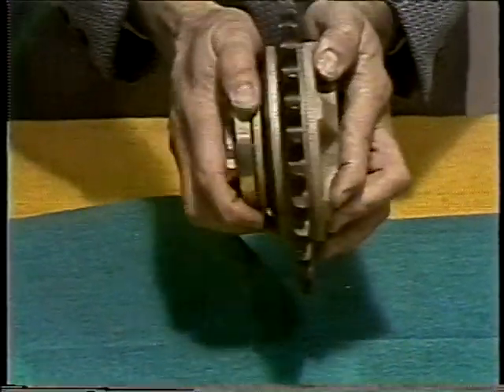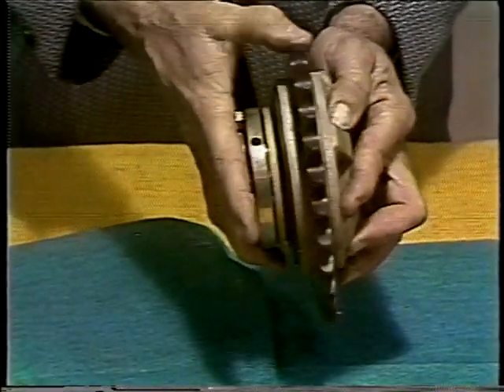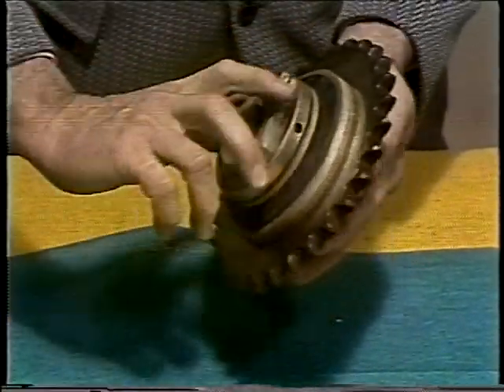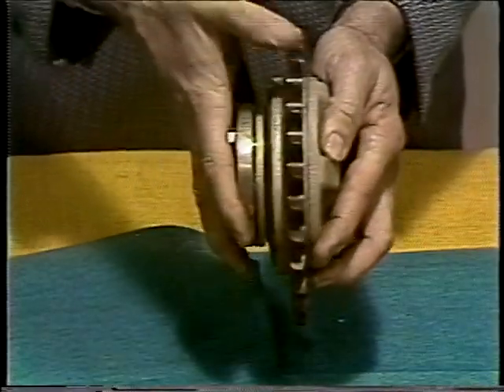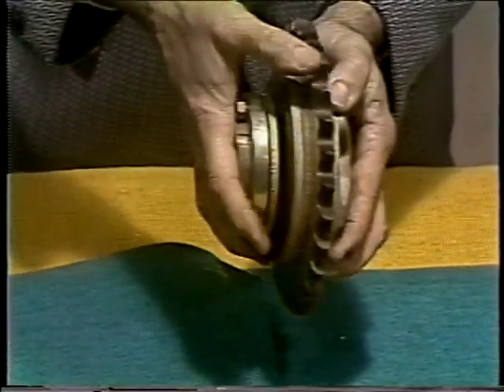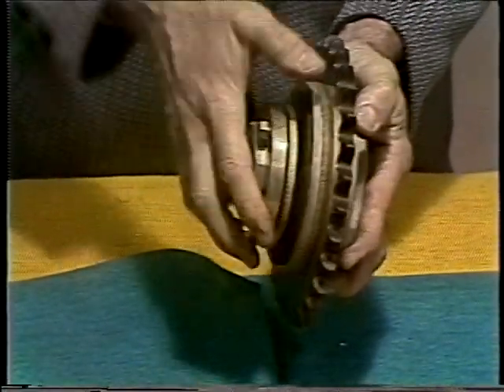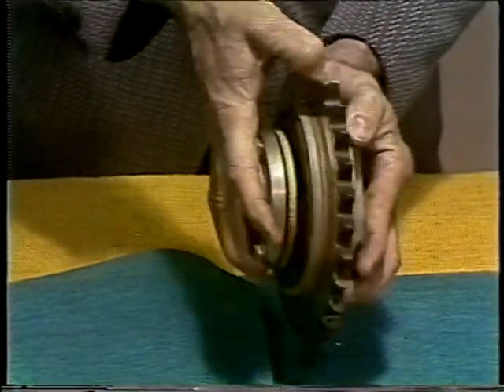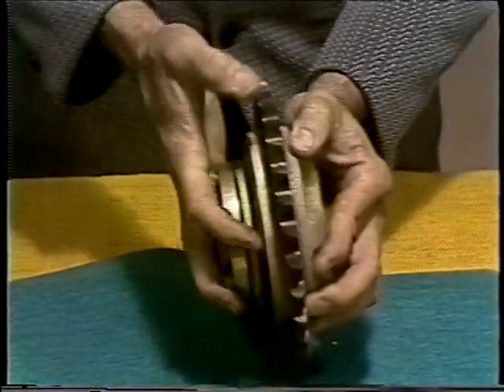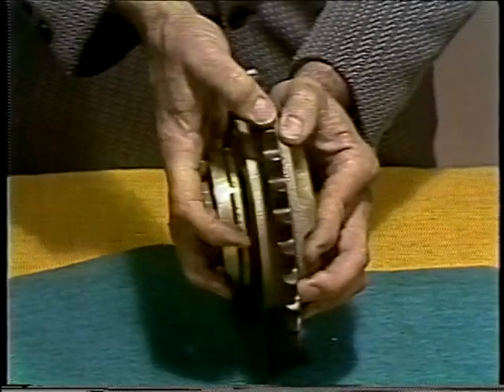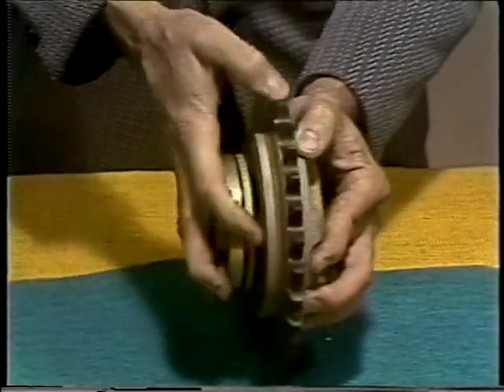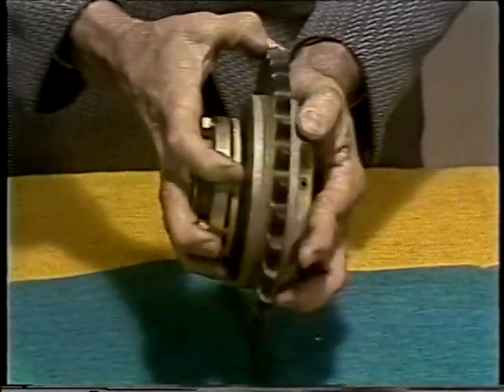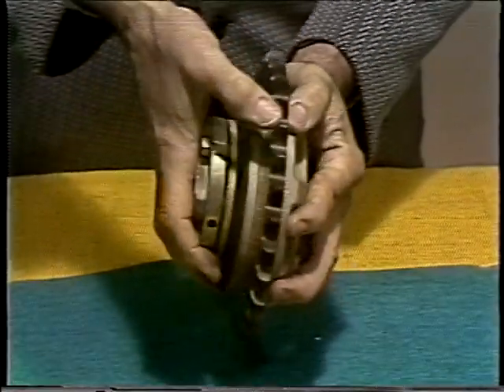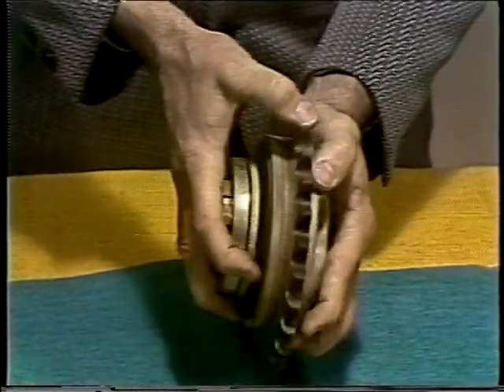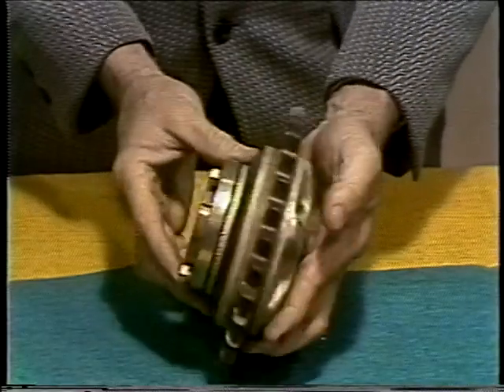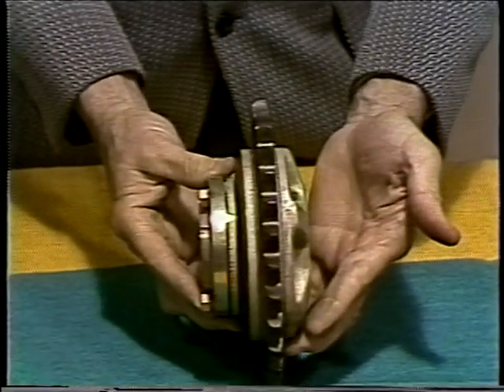Now by tightening or loosening the nut, we can vary the point at which the disc will slip. When the amount of torque which the unit is able to transmit is exceeded, the unit slips. If you'll remember from the other tapes, torque is the twisting force in a shaft. This unit allows us to have a predetermined amount of torque designed into a system which prevents overloads.